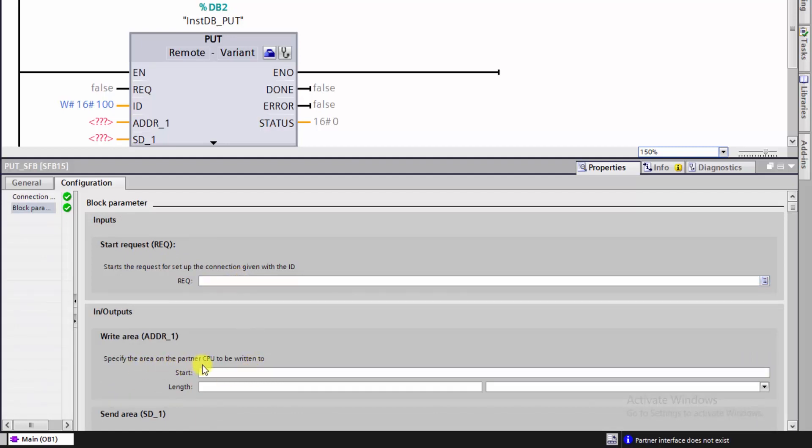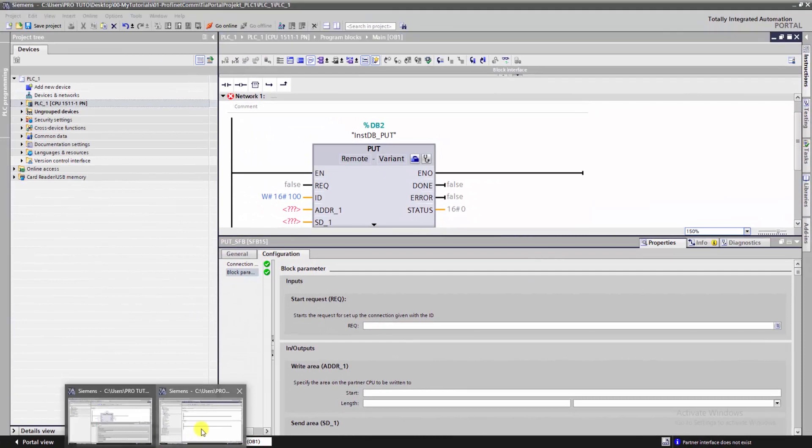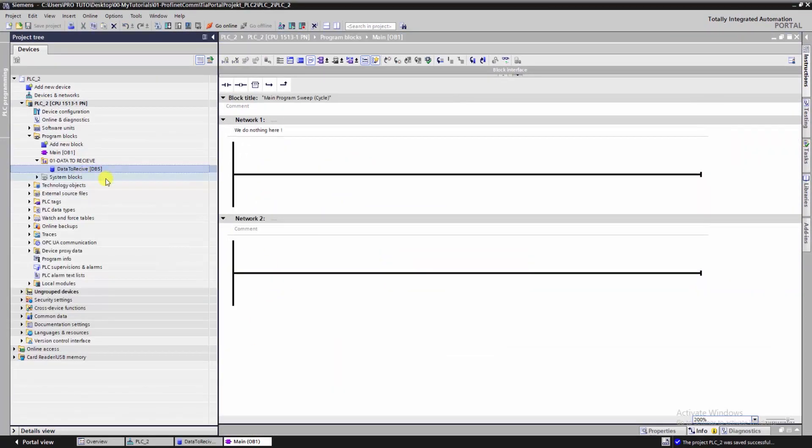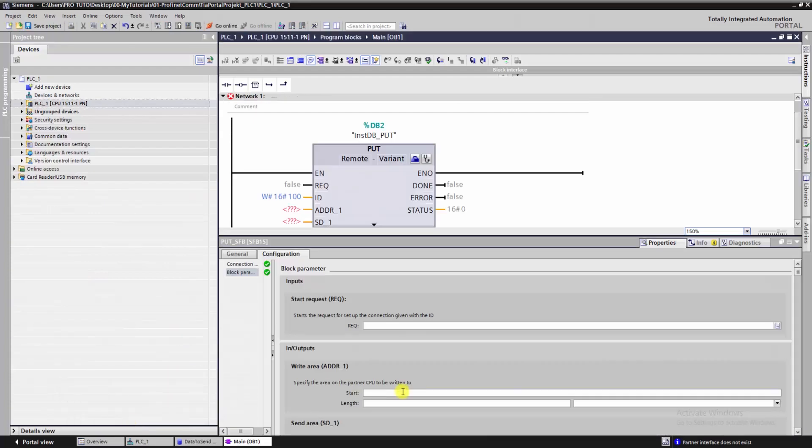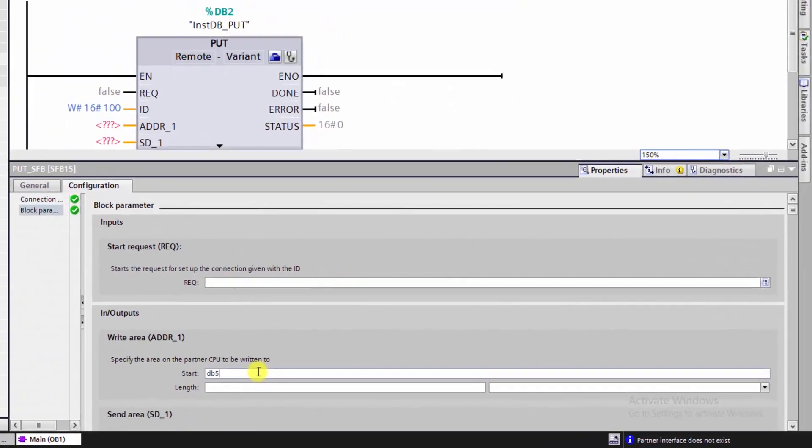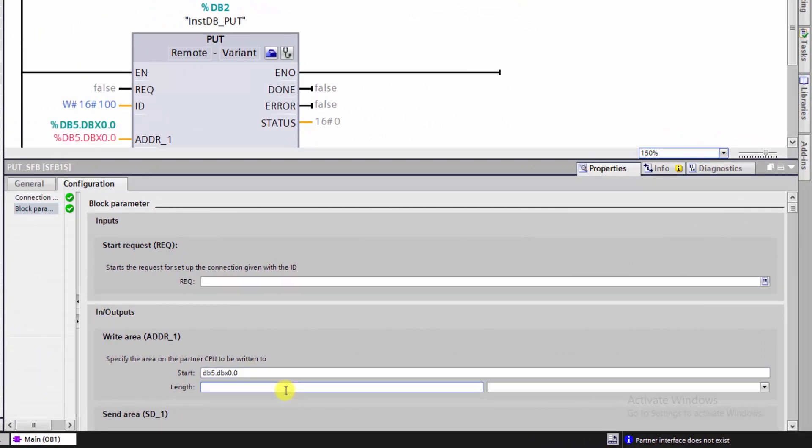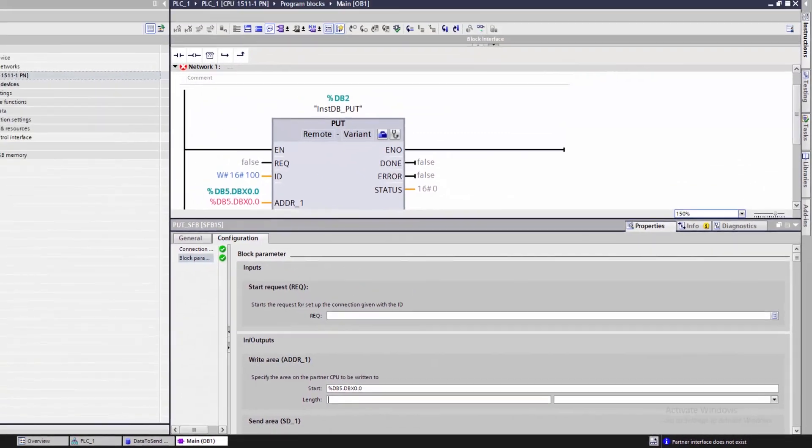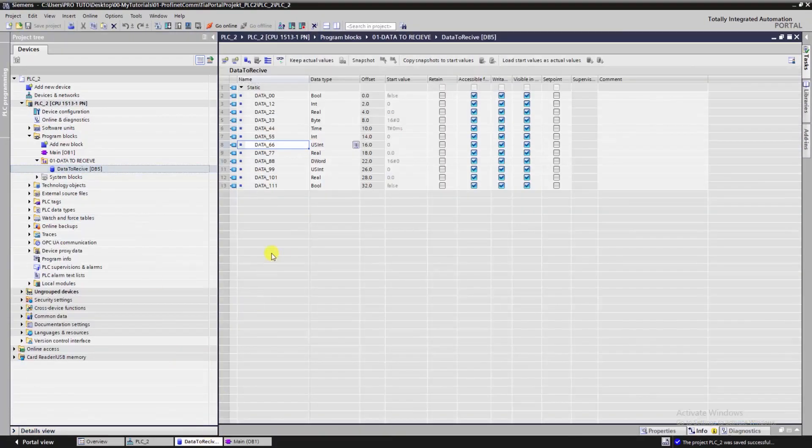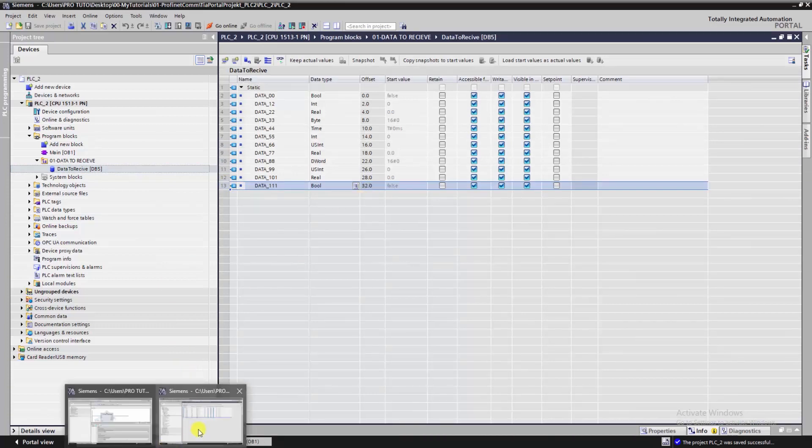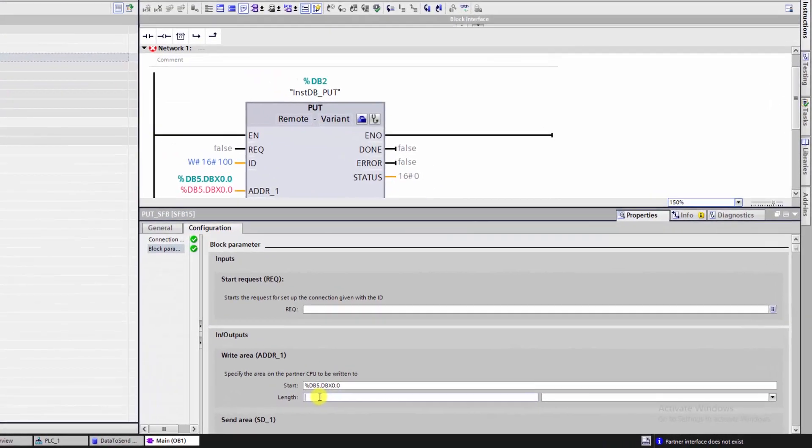Now, we have to mention the destination and the source of data we want to send. In our case, we want to put data from data block 1 in PLC1 to data block 5, PLC2. Also, we have to mention how many data we want to put and starting from which address. In our case, we want to send 32 bytes starting from the first element of data block.